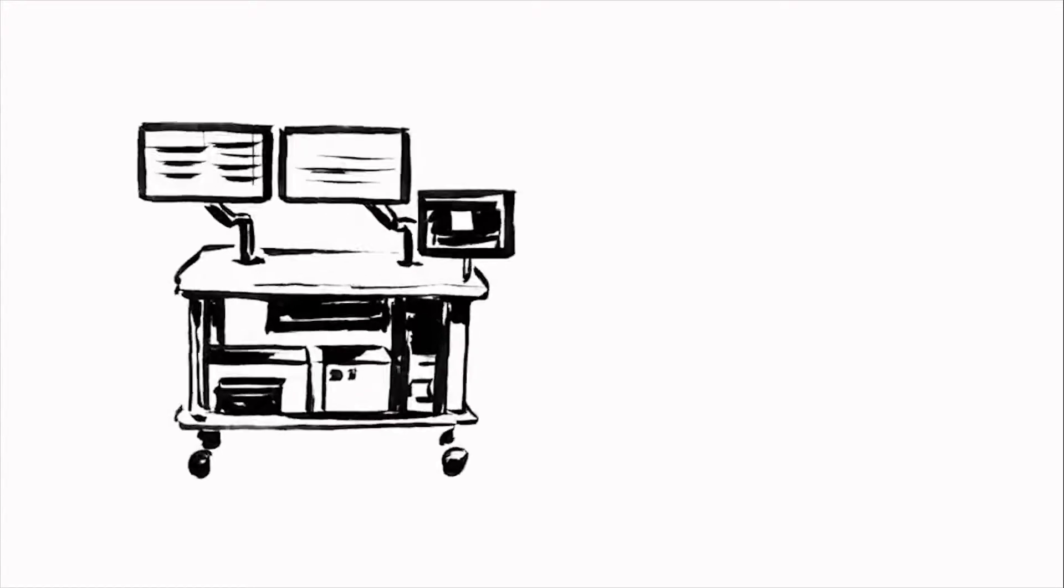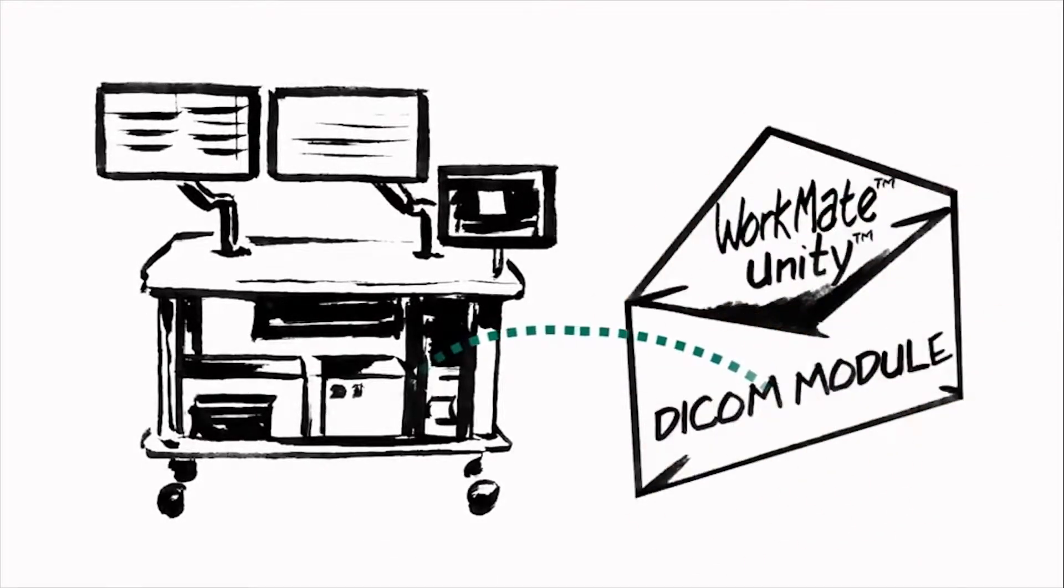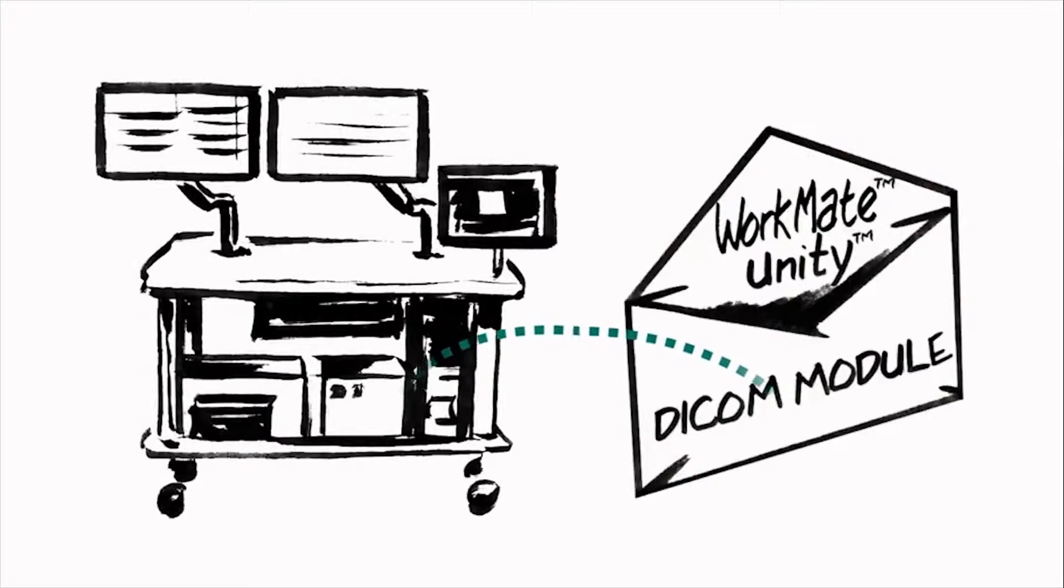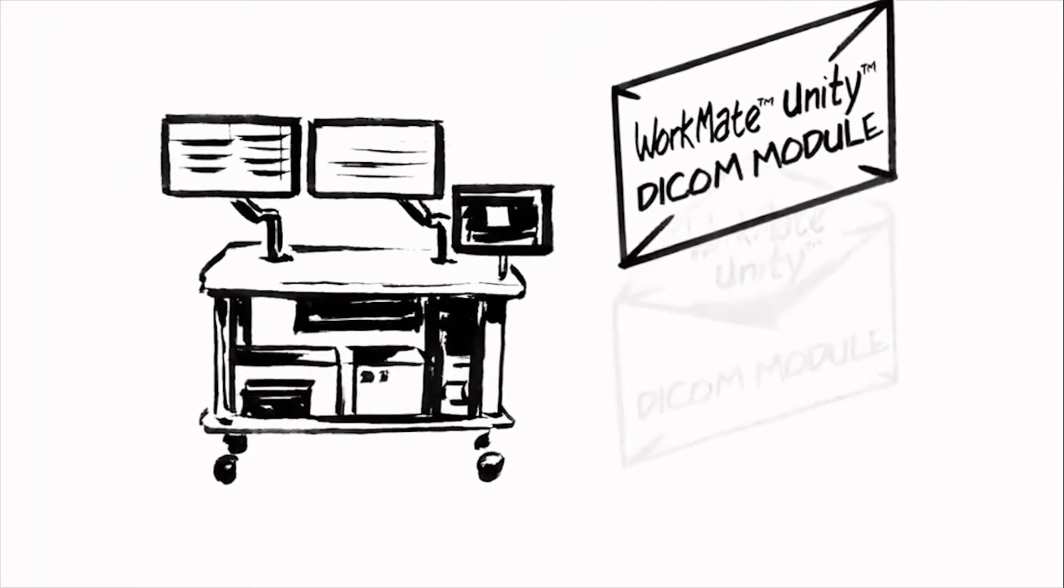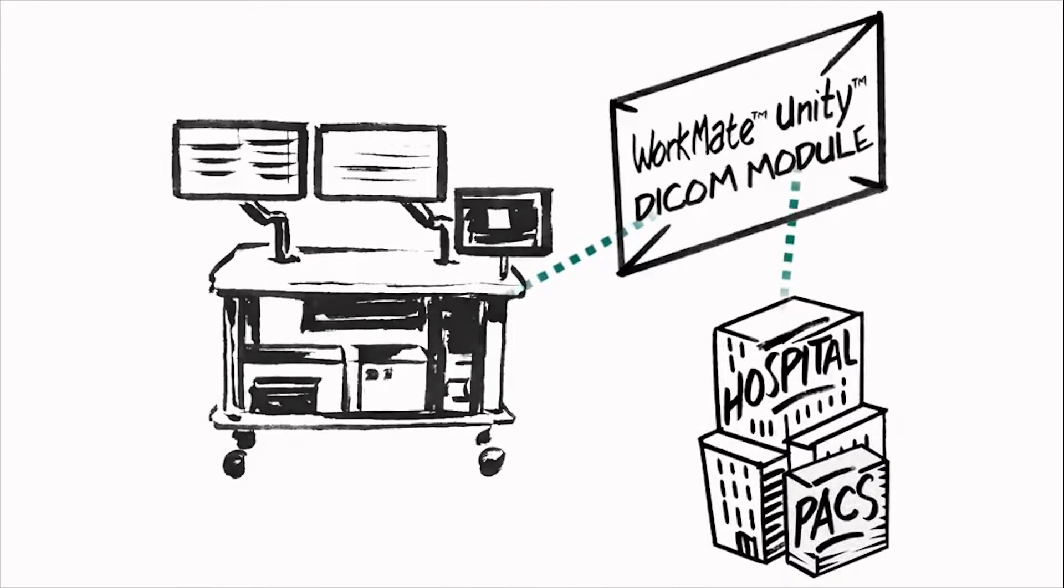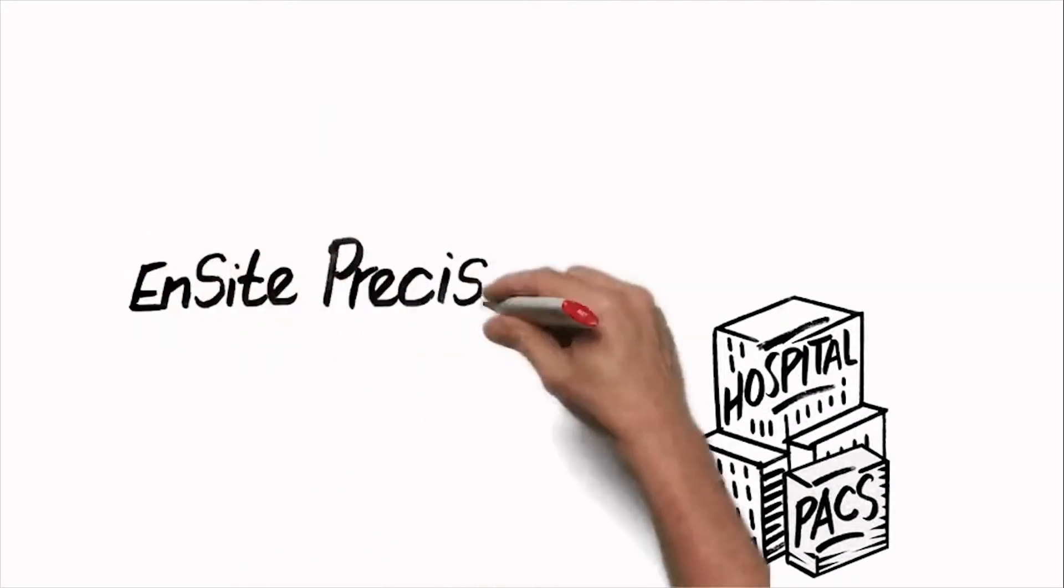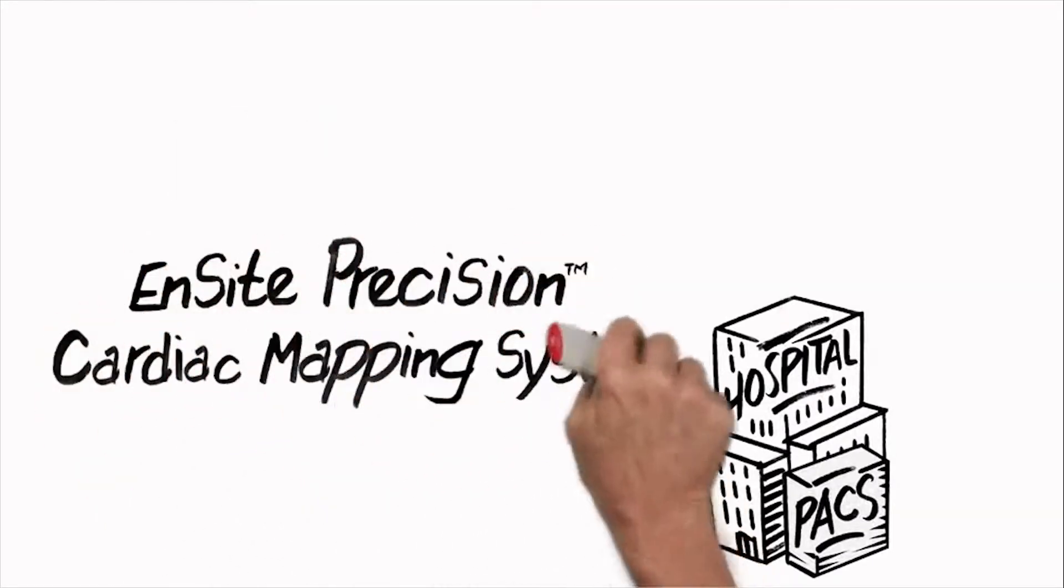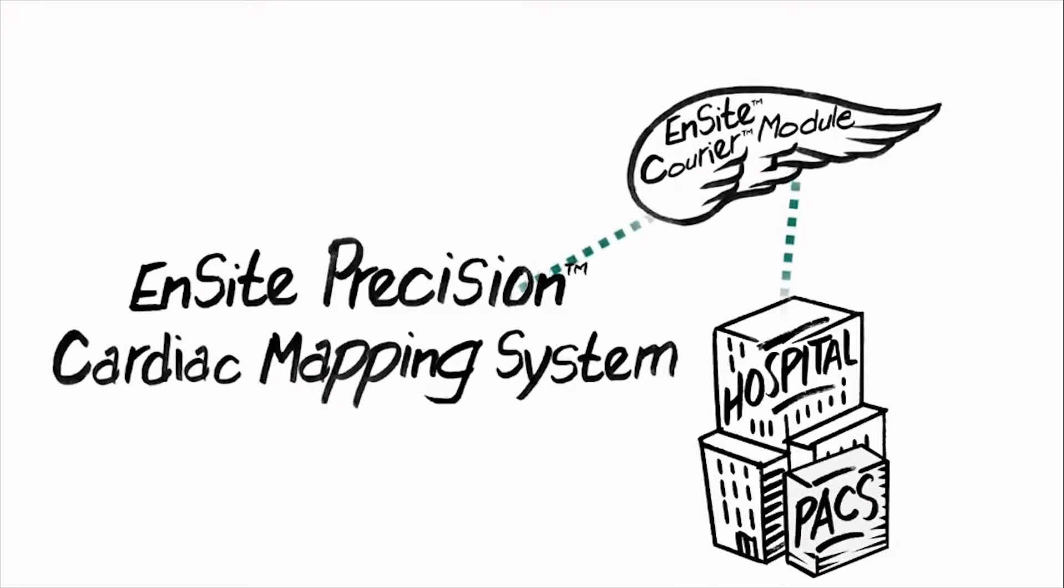The Workmate Claris system is not a standard medical imaging modality supported by PACS. Therefore, the Workmate Unity DICOM module effectively overcomes this compatibility issue by wrapping the case data from the Workmate Claris system inside of a DICOM compatibility envelope, allowing Workmate Claris to seamlessly store the data on the hospital PACS. The EnSite Precision Cardiac Mapping System employs a similar technique to store procedure data to the hospital PACS via the Courier module.